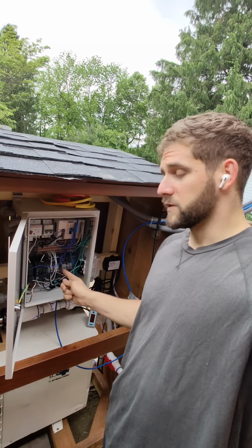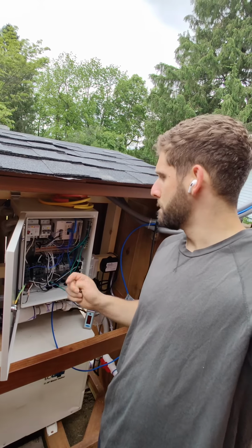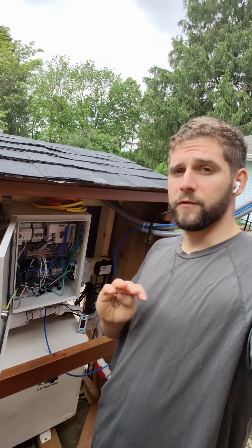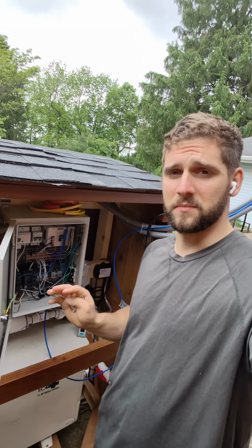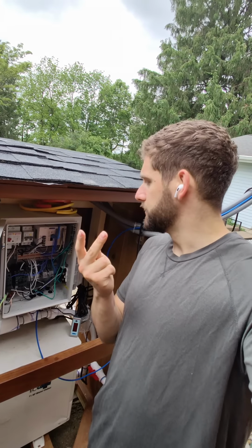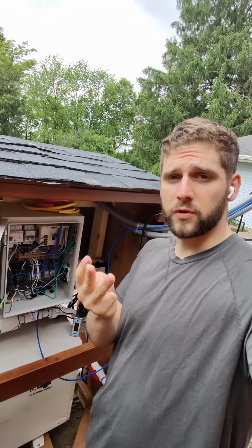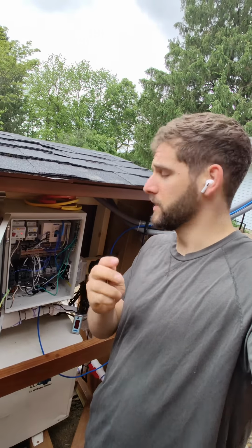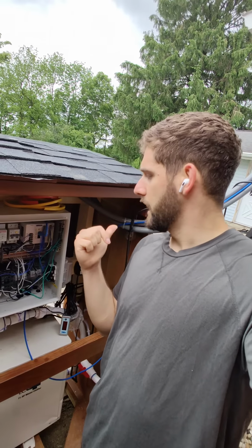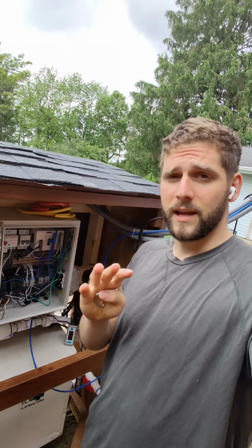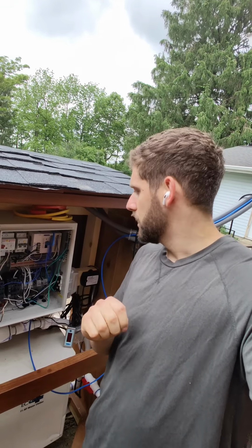There's some other stuff here I can go into more detail about, but this allows you to have full control of your entire system. There are temperature probes on here, flow sensors on here, and output controls, so it controls the chiller, the pump, the ozone generator, and the heater. It controls everything, and you can literally write it - it's not code, it's called ladder logic, and it's a lot easier to read than code. It kind of looks like a wiring diagram, but everything's labeled.